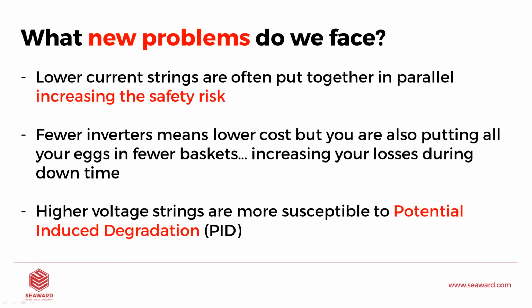We might have 3, 4, 5 strings at 6 amps, and again, you can see the inherent safety risk there, that we have a lot more current at the fuse, not to mention the increased voltage. That was why with our Solar Utility Pro, we decided that we wanted a very high rating on the short circuit current side. So this unit will operate at 40 amps DC, 1500 volts DC. So what that means is you can test multiple strings in parallel quite easily with our instrument.